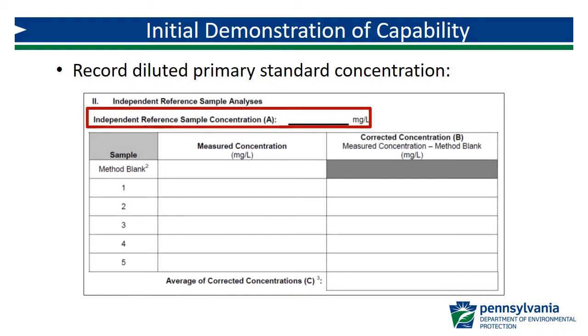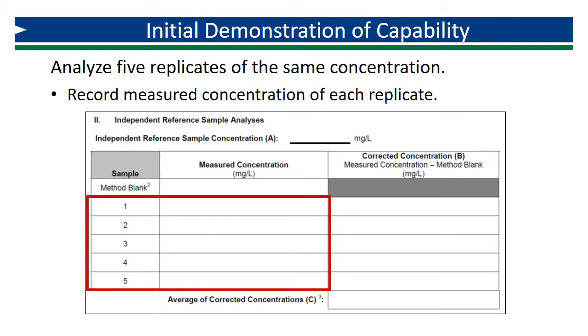Looking back at the IDC form, the aqueous check standard concentration is recorded in the field called Independent Reference Sample Concentration. This is the concentration of the prepared or diluted primary standard. Once you have prepared your diluted primary standard, you will analyze five replicates and record each result in the corresponding field under the measured concentration column. It is critical that each replicate is run as a discrete sample with each step repeated from beginning to end.